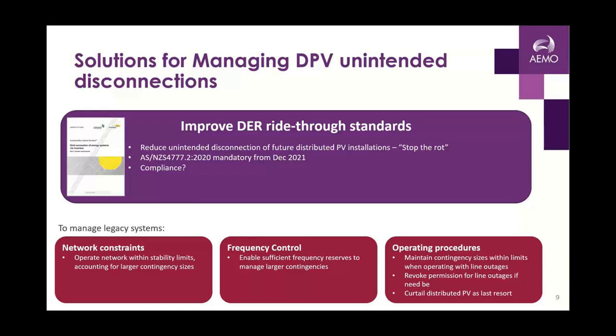So, some of the solutions for correcting this issue. The big one that we've already worked on is improving our distributed energy resource ride-through standards. That means that if we can program the inverters so that, if they were to see this event, instead of disconnecting they remain riding through, then that would help reduce that risk. We're calling it "stop the rot", because it would effectively minimize how much of that PV disconnects in consequence. We've worked very extensively on this, and Peter was part of the committee as well. The standard was published in December 2020, and then became mandatory a year later, allowing the manufacturers and everybody to uplift their requirements.